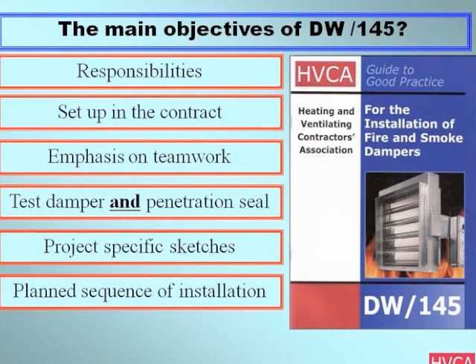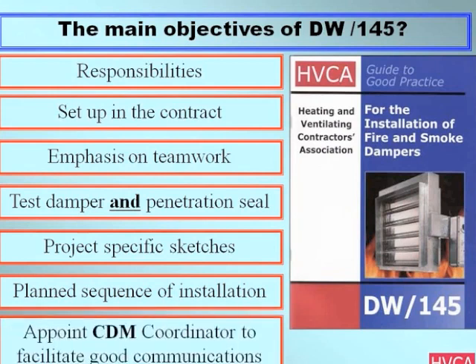So it's important that all parties recognise that to achieve a compliant installation, you've got to have the full sequence of activities. A major factor in achieving a compliant damper installation is that the contract should have a CDM coordinator to facilitate good communications.